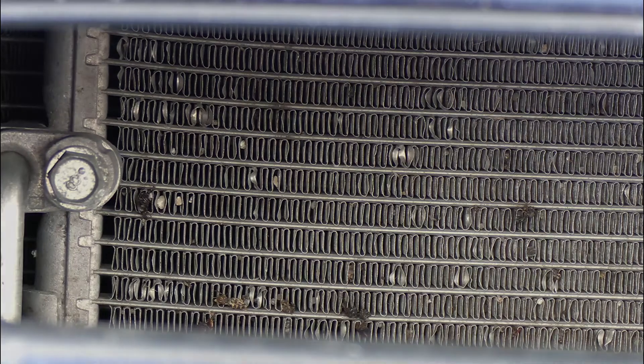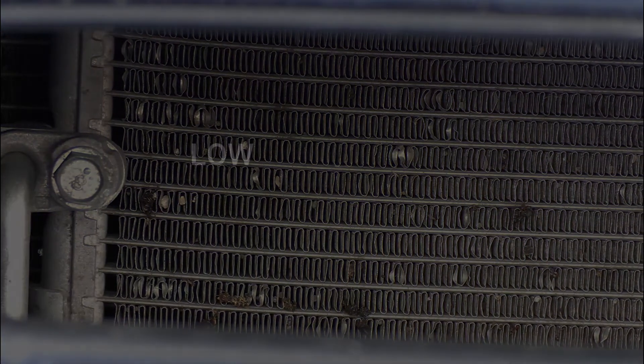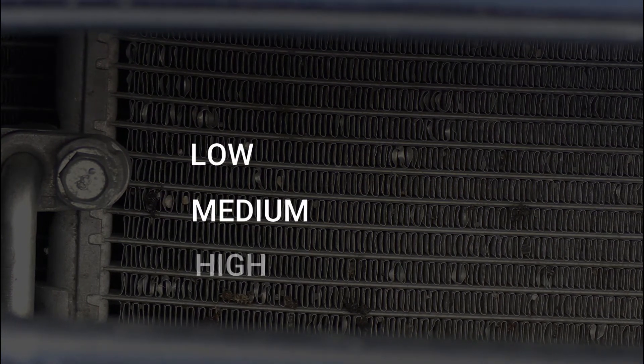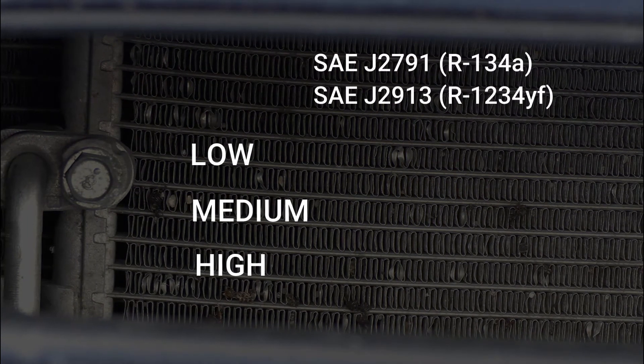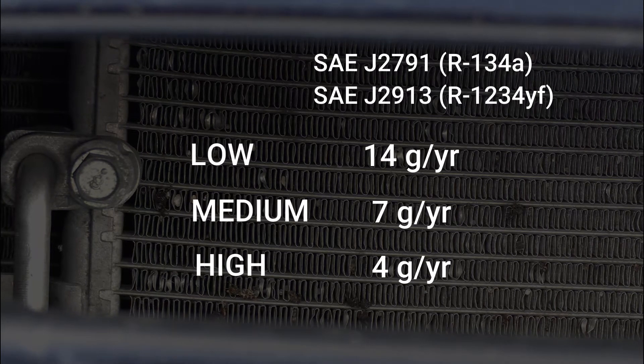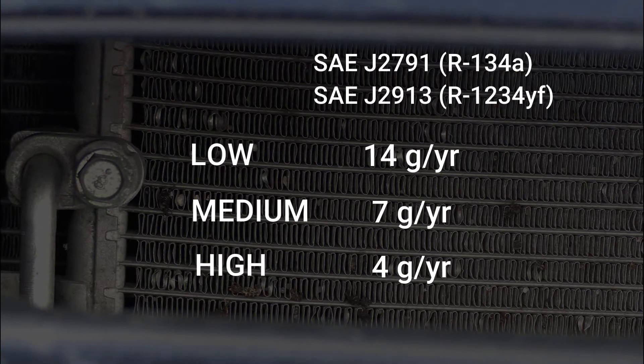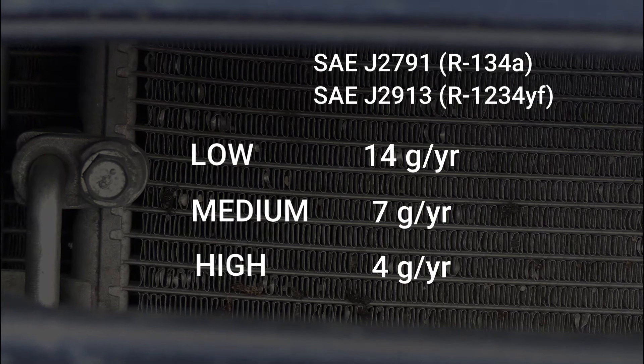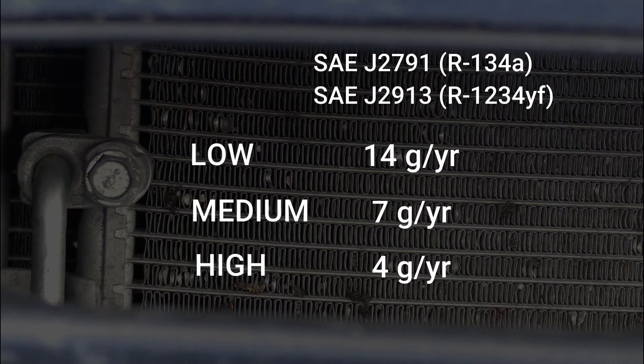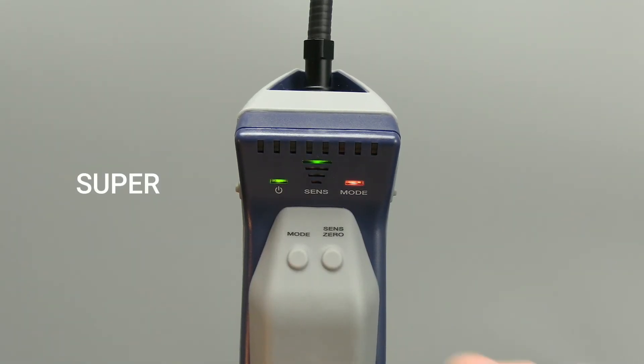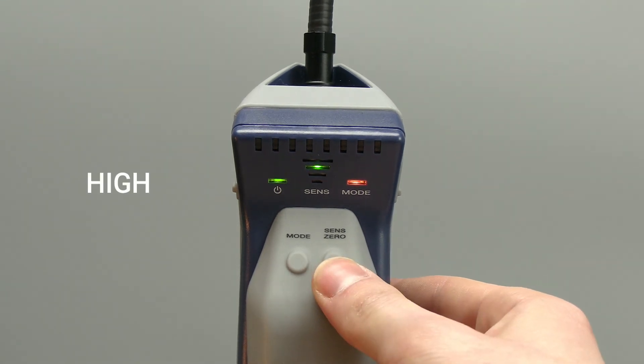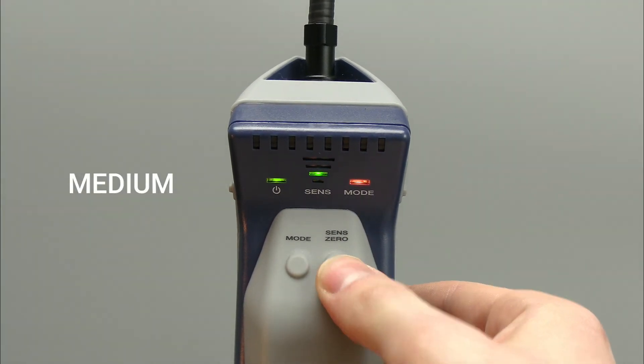AST 200 IR has four sensitivity levels. Low, medium, and high can be used to find leaks according to SAE J2791 and J2913 guidelines. Super sensitivity can be used to find even the smallest leaks. Press the sense zero button to toggle between sensitivity settings. The sense indicators show the current sensitivity setting.